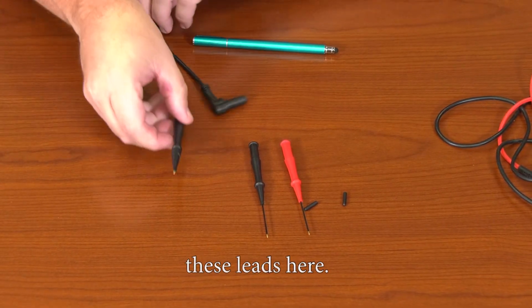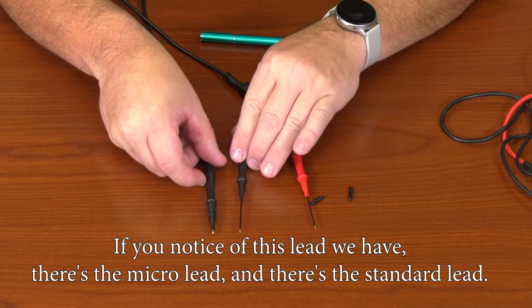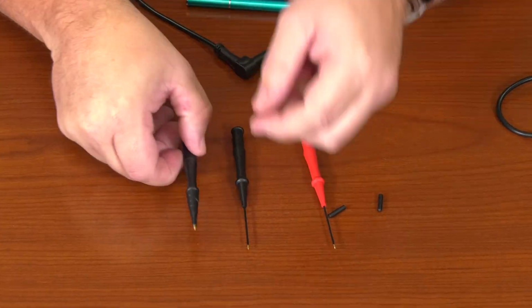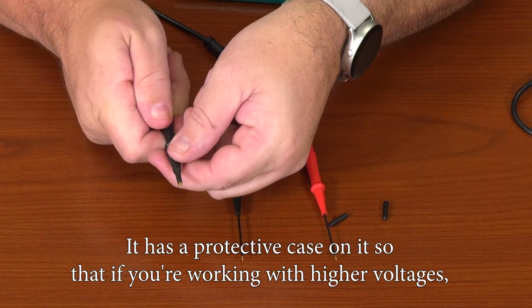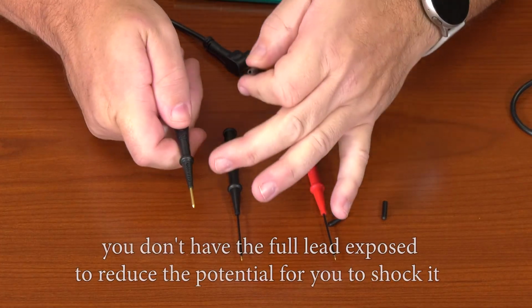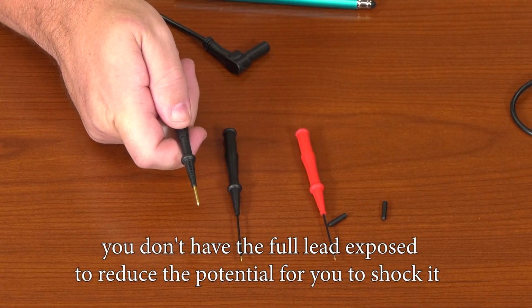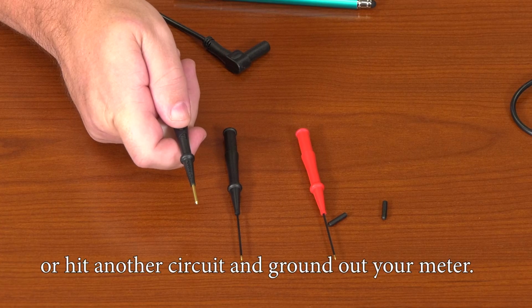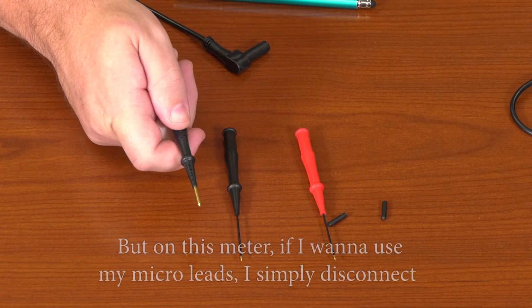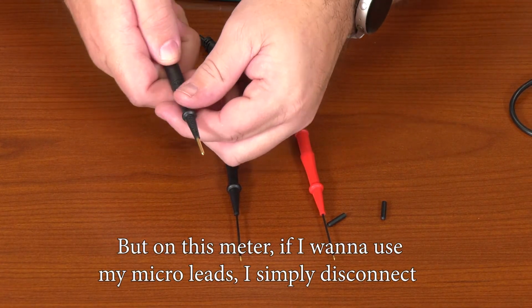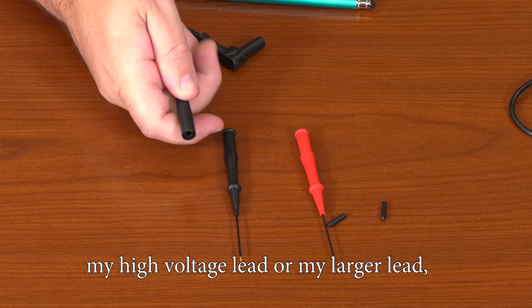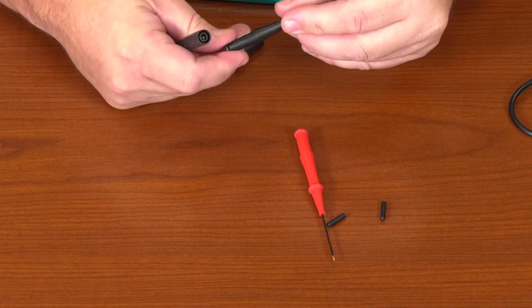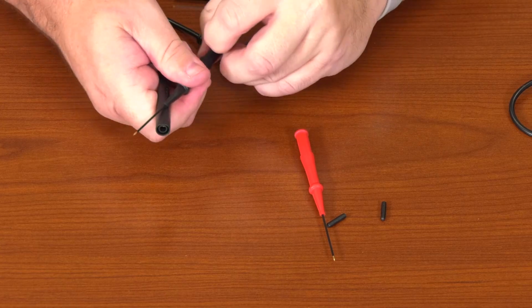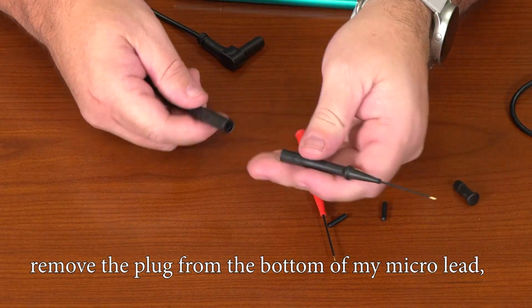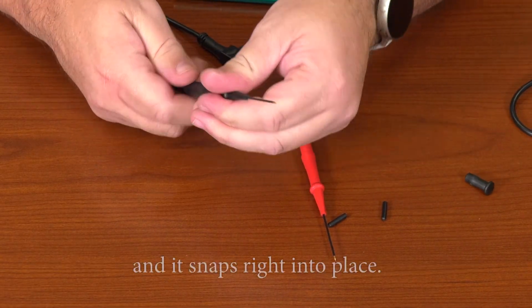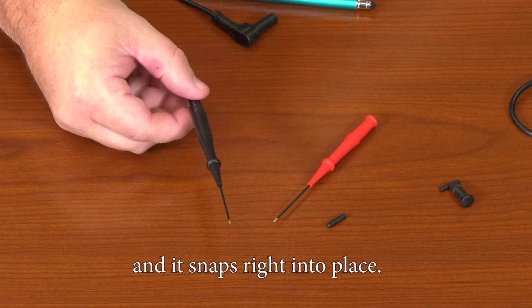these leads here. If you notice on this lead, there's the micro lead and there's the standard lead. It has a protective case on it so that if you're working with higher voltages, you don't have the full lead exposed, to reduce the potential for you to shock yourself or hit another circuit and ground out your meter. But on this meter, if I want to use my micro leads, I simply disconnect my high voltage lead, or my larger lead, remove the plug from the bottom of my micro lead, and it snaps right into place.